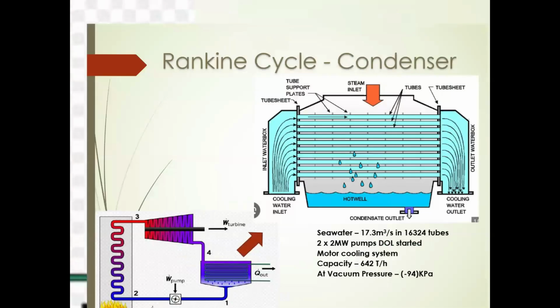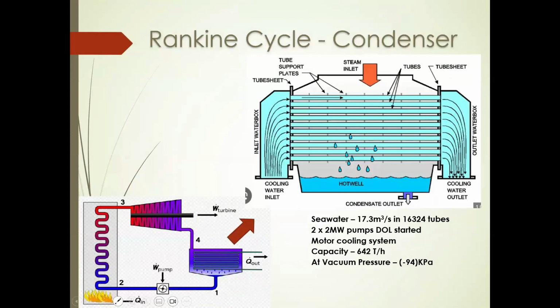Right. Now finally, the condenser. The LP turbine exhaust comes on top of the condenser. So the steam inlet comes to the condenser from the top portion. There are about 16,000 tubes in the condenser. Inside these tubes, you have cooling water flowing. When the steam gets in contact with these tubes, it takes out the latent heat of the steam and condenses the steam into water. The water drops to the bottom and is ready to be used once again in the pump itself.